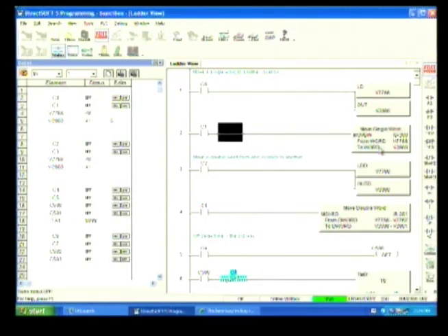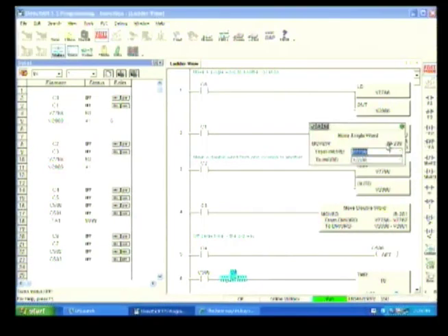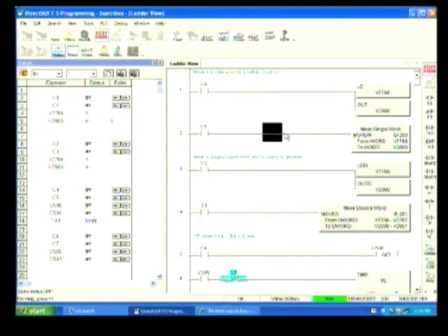Okay, now we get over to our iBox. iBox, one instruction. I know this doesn't seem like you're saving a lot of time, but it is. This is just a simple one, and then we'll get to the harder ones. You're going to move from one word to the next, and it's basically the same thing there, just moving the same location, V7766 to V2000. Move a double word. Well, instead of an LD, you're using an LDD, and you're going to out to a double word.